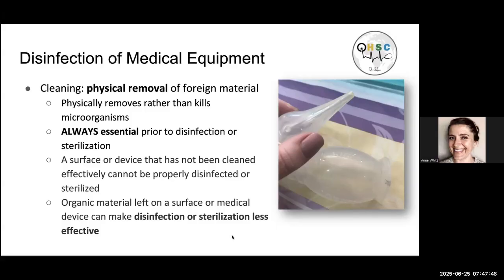And so we know that the equipment we use to care for babies can, in fact, transmit pathogens that will make babies sick. And so when we talk about disinfection, there's a lot of terminology that gets used interchangeably, but these terms really do mean some different things. And so when we talk about cleaning, cleaning is the first step in a disinfection and sterilization procedure. And cleaning really refers to the physical removal of foreign materials. Cleaning, for example, with soap and water, doesn't kill organisms, but it physically removes them. It washes them away.